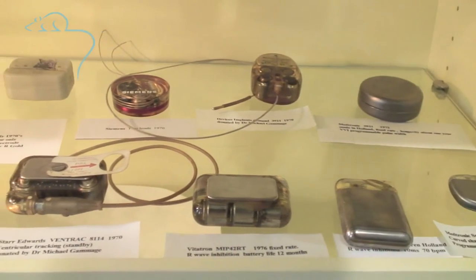The battery life depends on how hard the pacemaker has to work — whether it's just working intermittently or whether the patient requires the pacemaker all the time. But on average, lithium batteries today will last between six and ten years. When the battery is nearing its end of life, the patient will be asked to come to the hospital for a battery change.